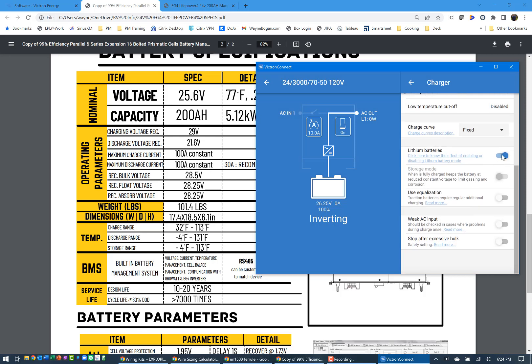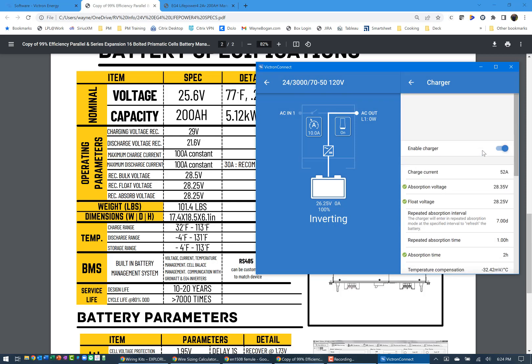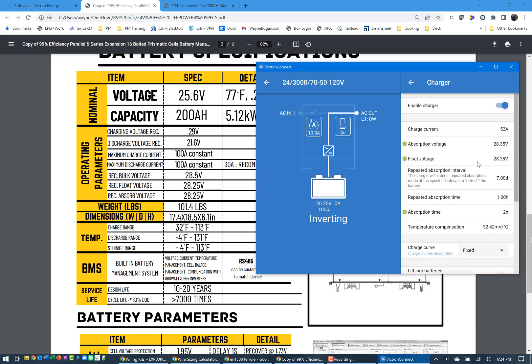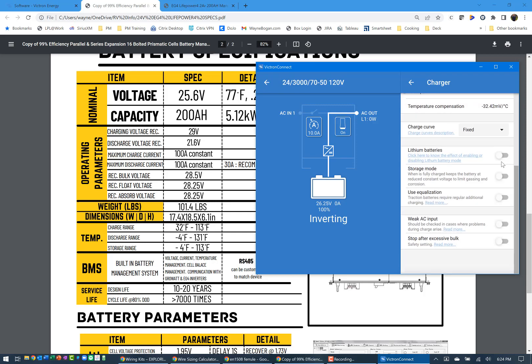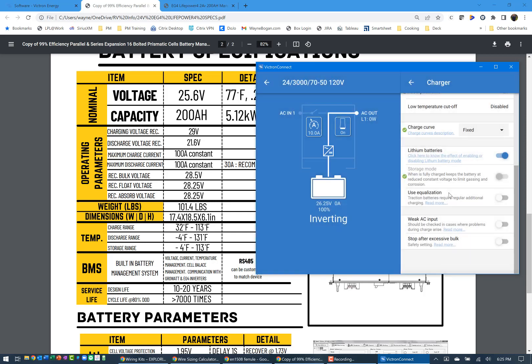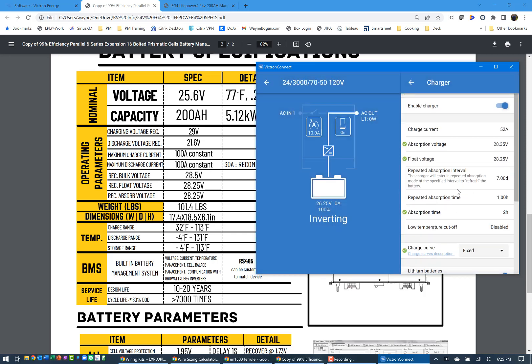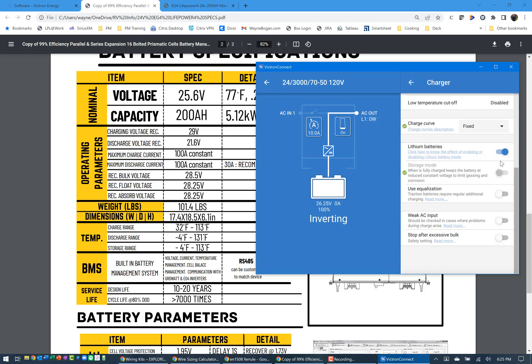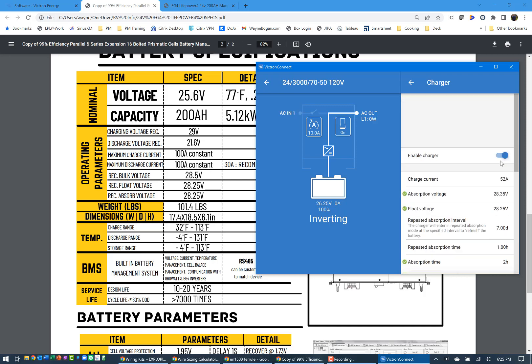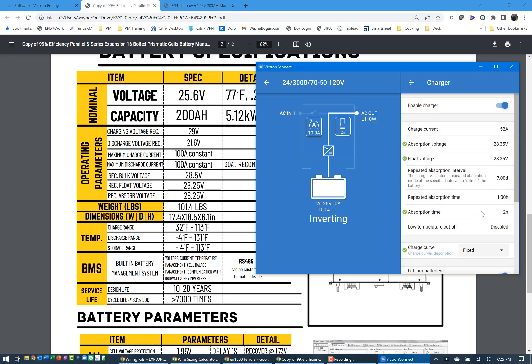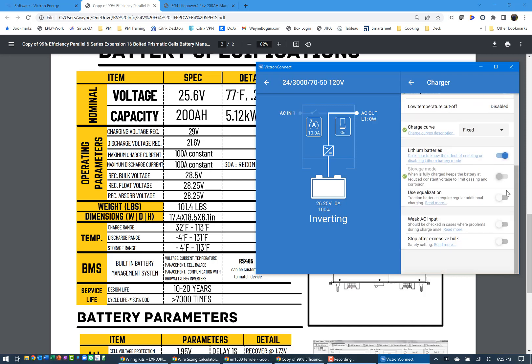You also have to change lithium batteries. So you'll notice this changes the settings there. So you turn on lithium, come back and verify your settings. Charge at 52, 28.35, 2.5, and I've got the absorption set at 2 hours. And then we'll leave the rest of these the same.